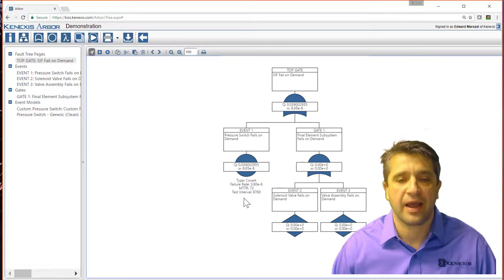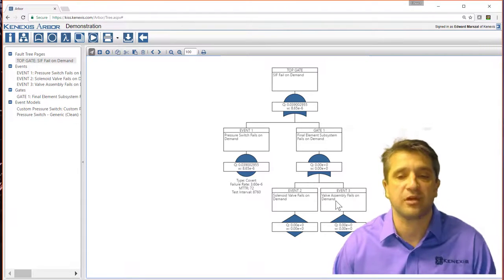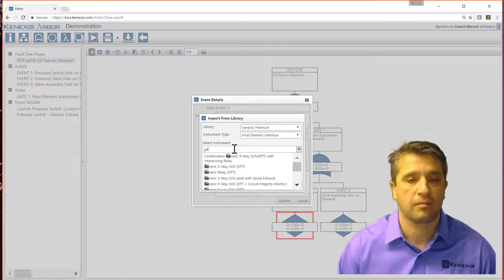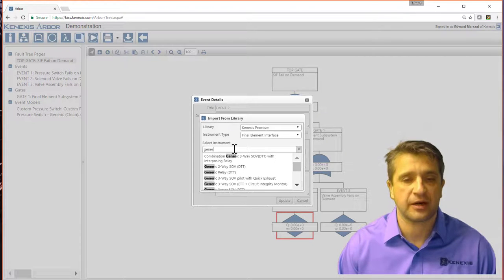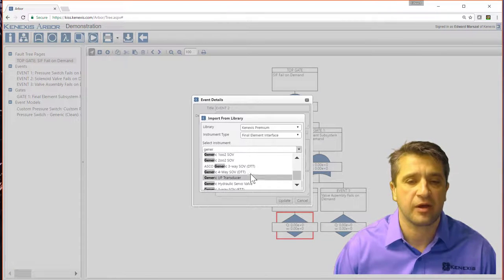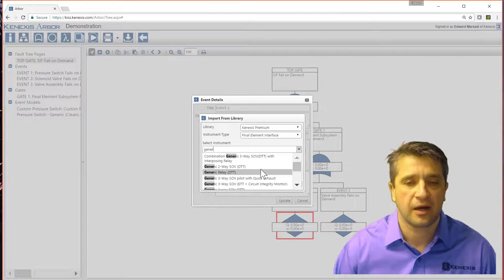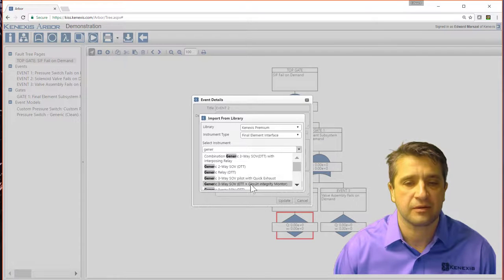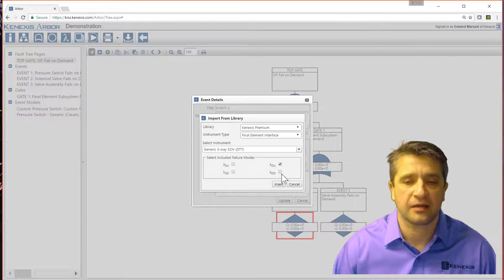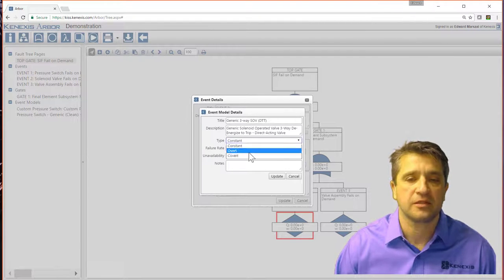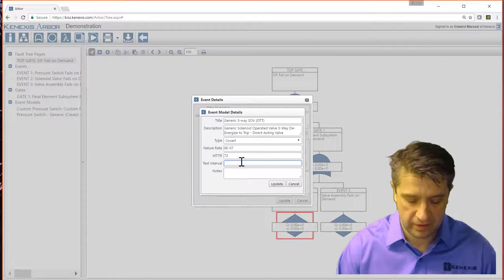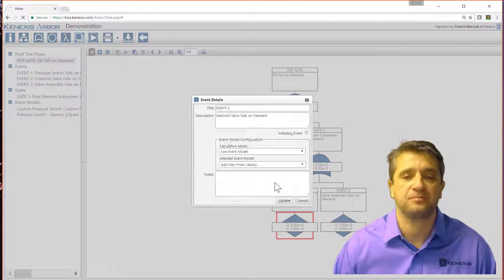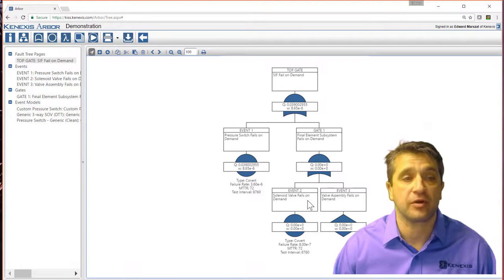And now I have a new model for pressure switch. So let me go ahead and do the same thing to the other items. I'm going to import the data for a generic three-way solenoid valve. Let's go ahead and say de-energize to trip generic three-way SOV. Dangerous undetected, dangerous detected. Hit insert. Select that it's a covert failure model with 72 hour mean time to repair. 8760 on the test interval. Hit update. And now I have all that data for the solenoid valve.